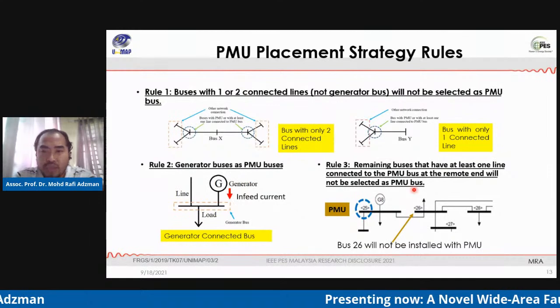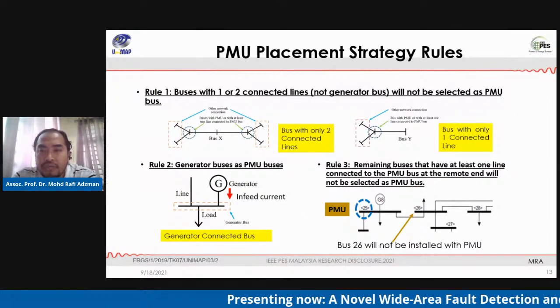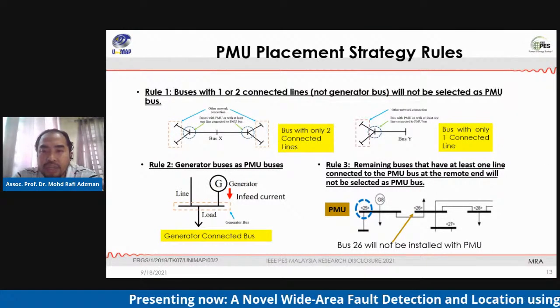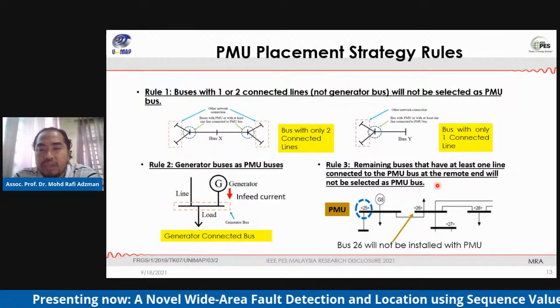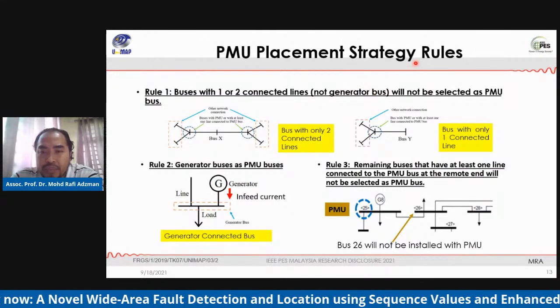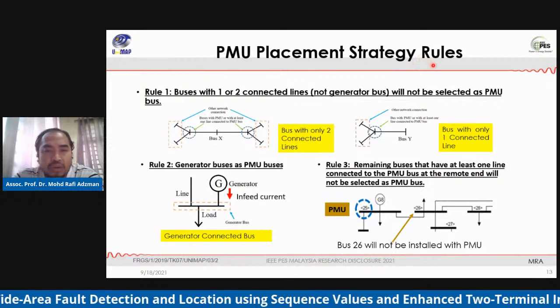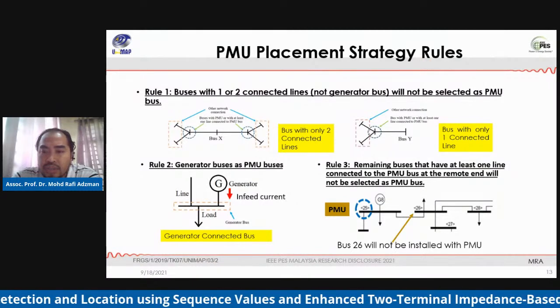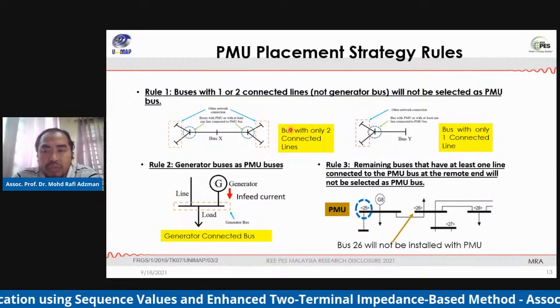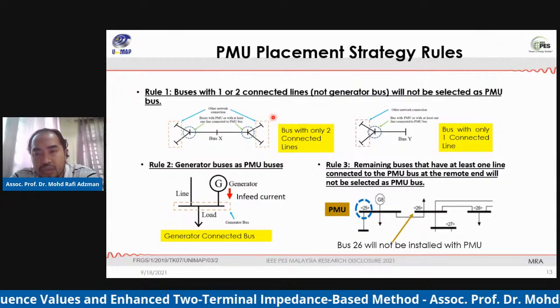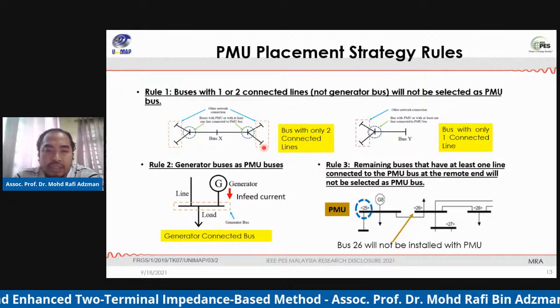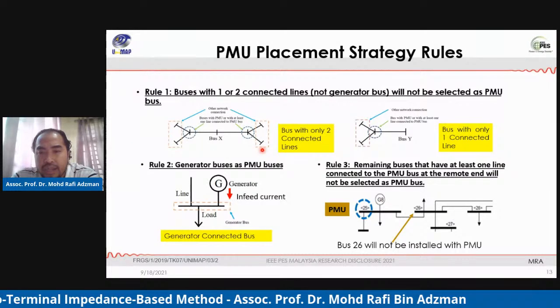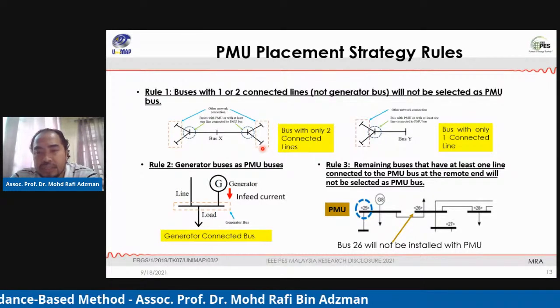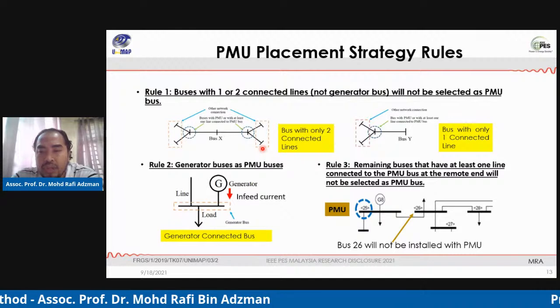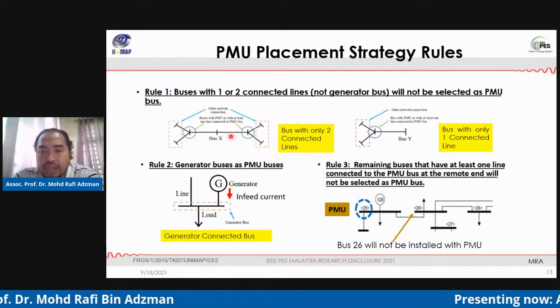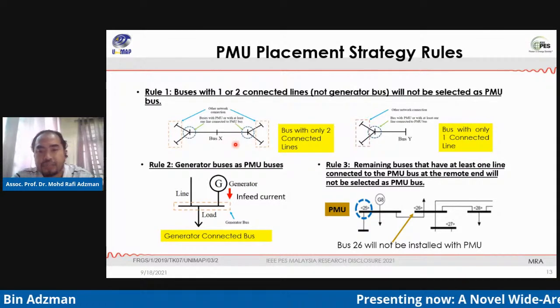Okay, in this work, before we use the fault detection and location algorithm, the PMU placement strategy needs to be applied, and the PMU placement strategy is based on 5 rules. For rule number 1, the bus voltage is calculated using the voltage from the adjacent buses, while the line current is taken from the adjacent buses where PMU is installed. If not installed, it will be calculated using the KCL.